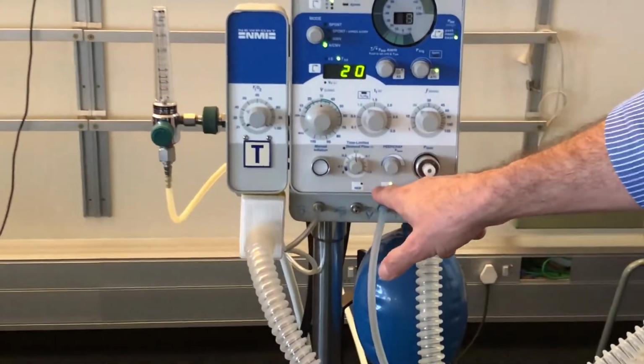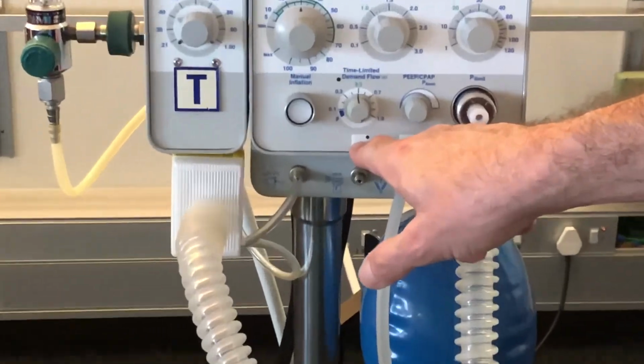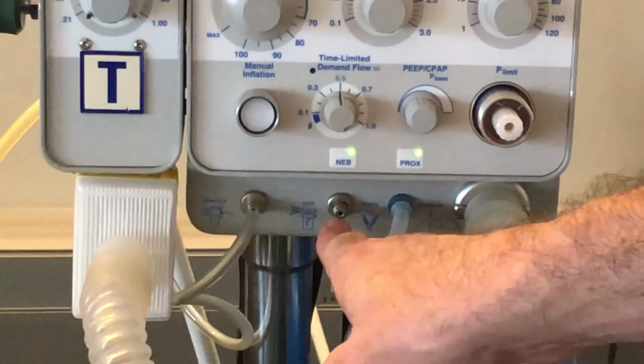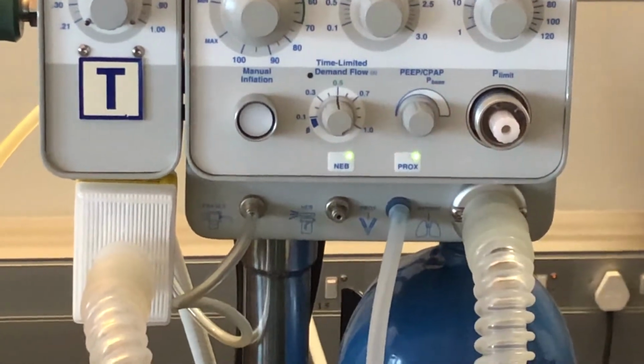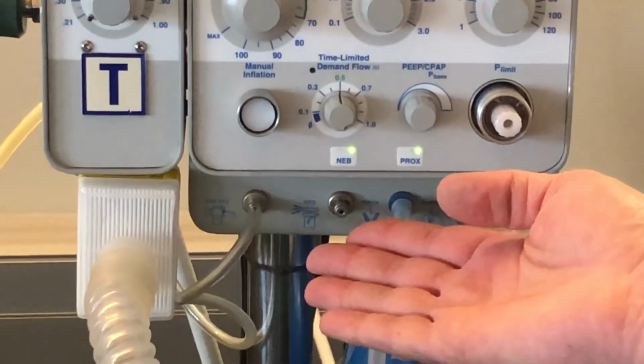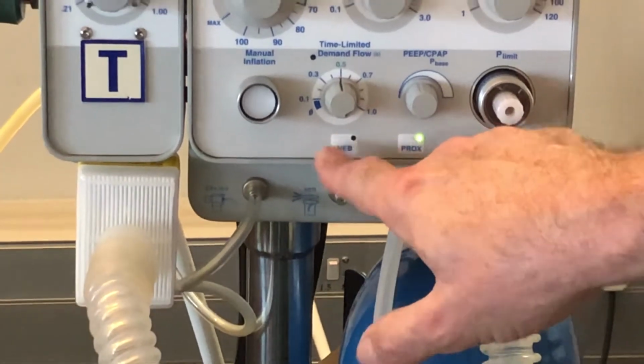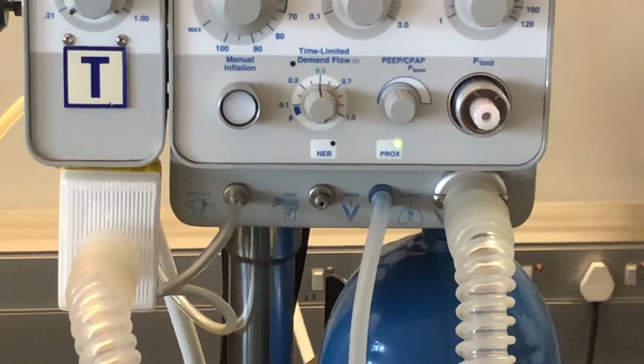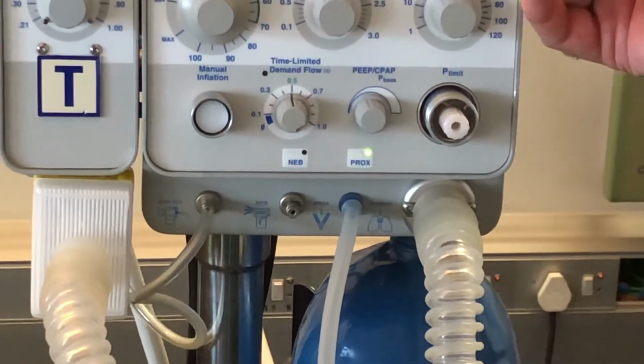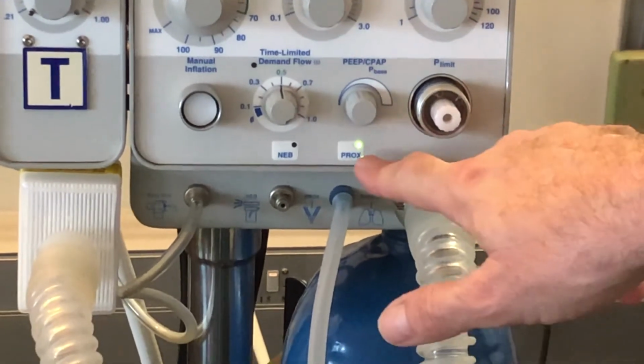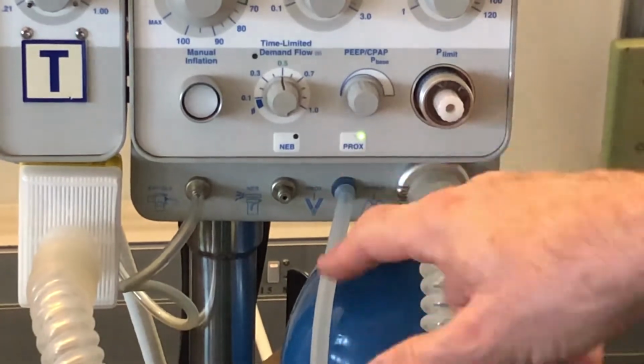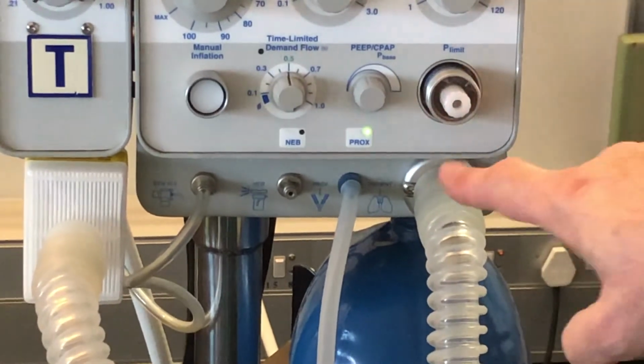Last two little buttons on the bottom here. The first one is neb. So if we switch that on, we can get the ventilator to drive a nebulizer. You can hear the gas coming out of it, and that just coincides the nebulizer activity with inspiration on the ventilator. And then the last thing here is where we want the machine to sense the pressure.